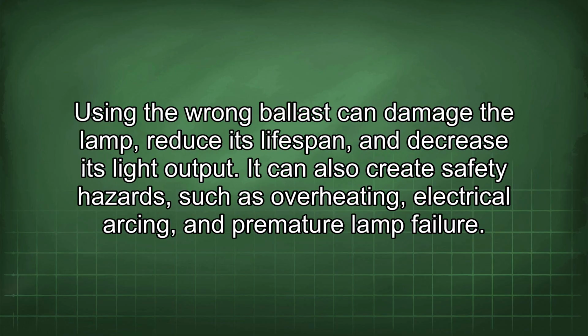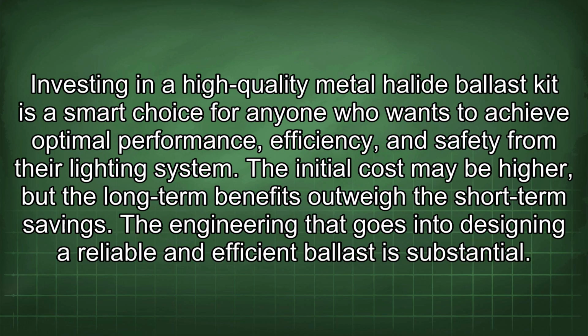Using the wrong ballast can damage the lamp, reduce its lifespan, and decrease its light output. It can also create safety hazards such as overheating, electrical arcing, and premature lamp failure. Investing in a high-quality metal halide ballast kit is a smart choice for anyone who wants to achieve optimal performance, efficiency, and safety from their lighting system. The initial cost may be higher, but the long-term benefits outweigh the short-term savings. The engineering that goes into designing a reliable and efficient ballast is substantial.